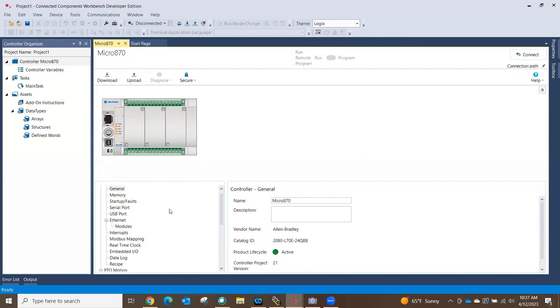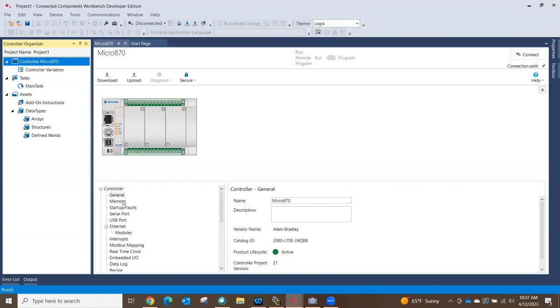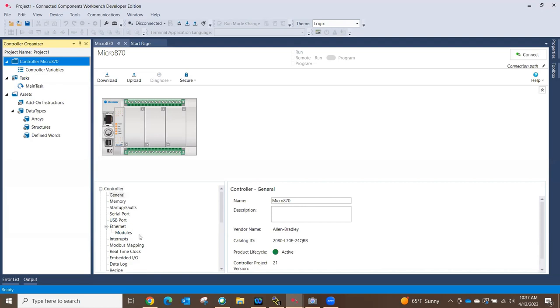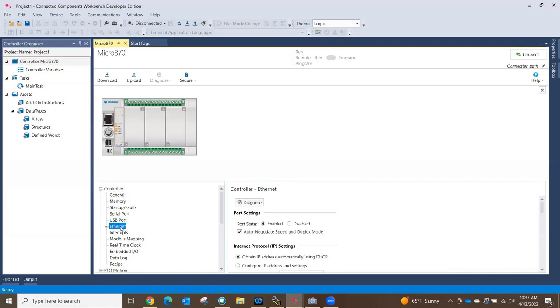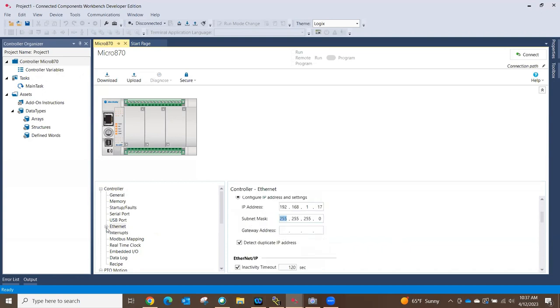I select my Micro 870 controller and double-click on it to bring up the configuration window. This is where I set up memory usage, configure serial ports, USB ports, and do Modbus mapping. We're interested in Ethernet — the first thing I'd do is give my controller an IP address and subnet mask. Then I hit the plus sign to go into modules. This is going to look a lot like an add-on profile for Studio 5000 Compact Logix — it's not, but it sure looks a lot like it.